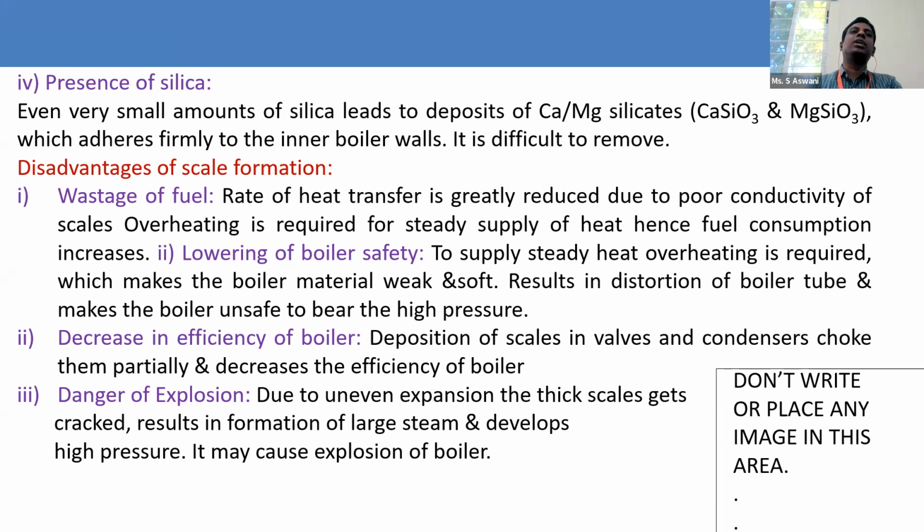So what is the disadvantage of scale formation? The wastage of fuel. We need more heat to generate the steam, so the consumption of fuel is enhanced. The rate of heat transfer is greatly reduced due to the poor conductivity of scales.